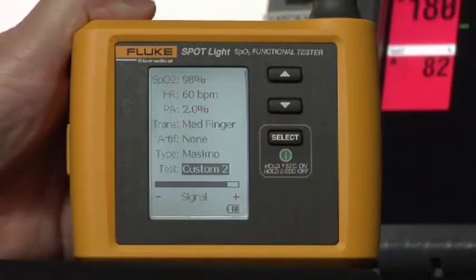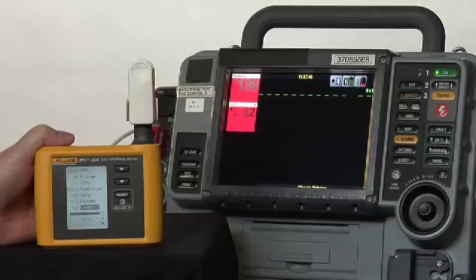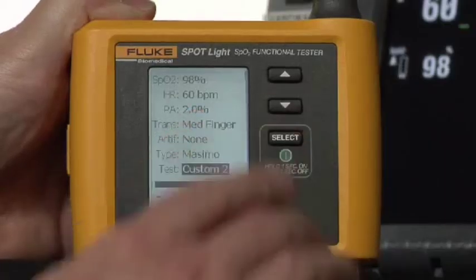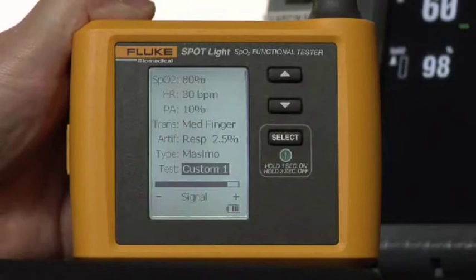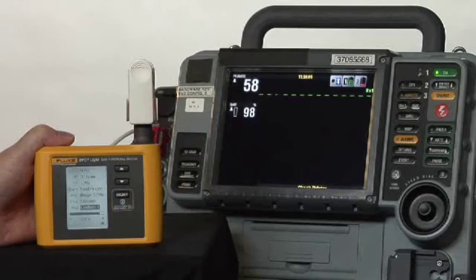And then we'll move to custom 2, which is a normal patient. We want to let the alarms continue to sound because the normal conditions will let them silence on their own, an important part of the functional test. Again, waiting for those to settle, and then we'll simply push one more time for our hypotensive patient with a low O2 saturation, low perfusion, and you'll see the alarms will sound again, this time on the low end.